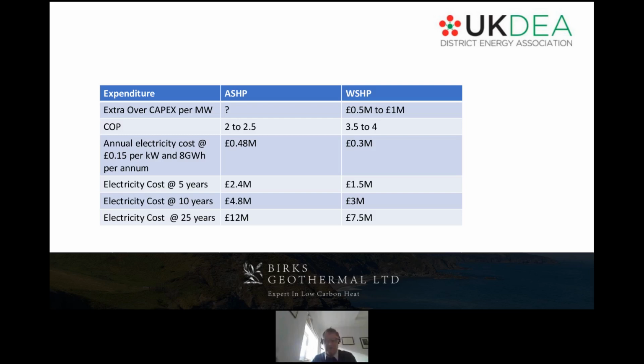We know that the coefficient of performance of an air source heat pump is lower than a water source heat pump: 2.5, versus 3.5 to 4 for a water source heat pump. So what does that actually mean in terms of Colchester Gateway? Assuming an electricity cost of 15 pence a kilowatt hour, and producing 8 gigawatt hours per annum of heat, so a modest size heat network, the electricity cost utilizing air source heat pump technology to provide that heat is just under £500,000. Whereas the same with the water source heat pump would be £250,000, so substantially lower within the first year.